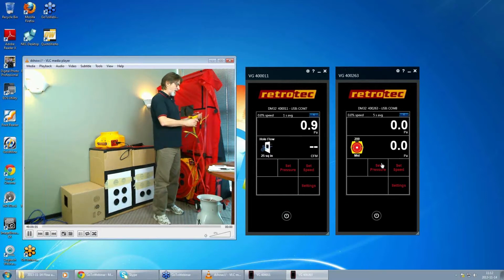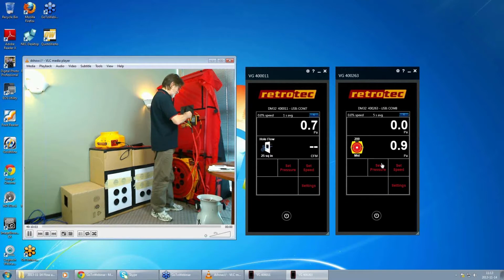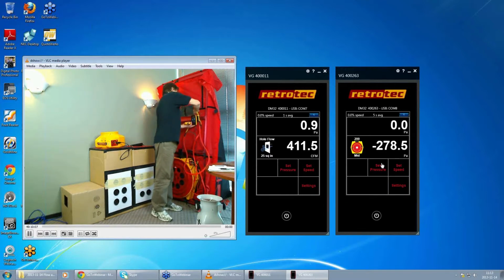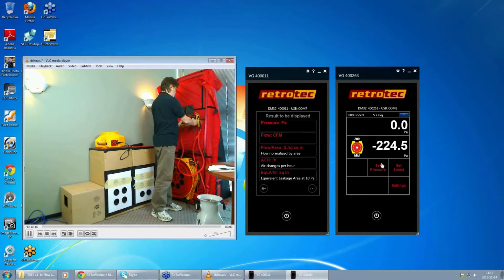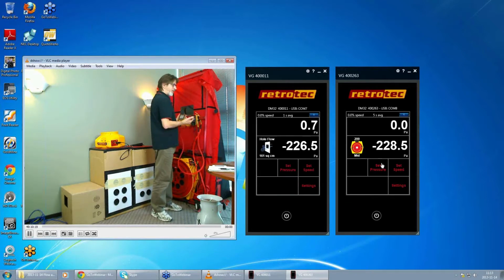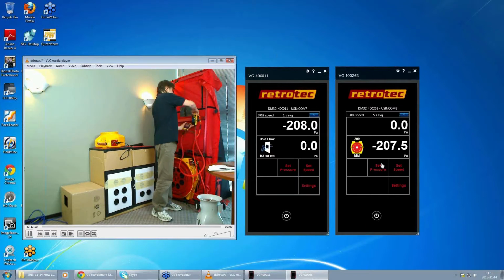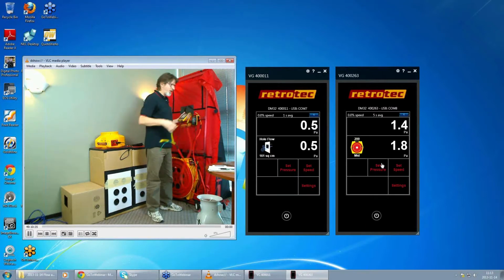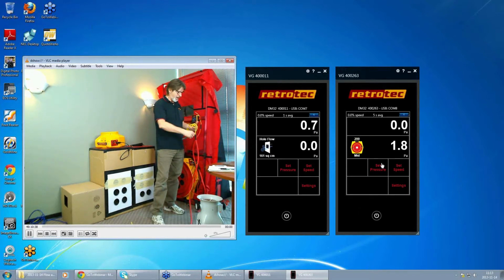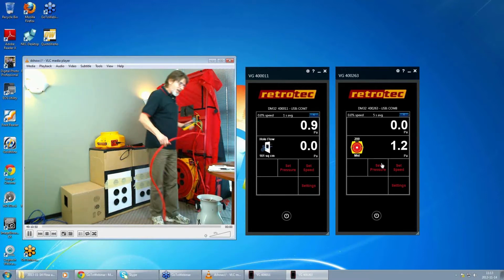You can also check this gauge between this gauge and another gauge to make sure that, in fact, we can do that right now. We can check this gauge here against this gauge over here. And we have to change this to pascals, of course. So 224, 225, it means this gauge is the same as that gauge. We can check the other channel in the same way. So we've got 208, 207. So this is meaning that both of these gauges are in good shape. I know there's a lot of talk about getting gauges calibrated on a regular basis. I think that's a lot of wasted time and money. And a gauge check should be something that gets performed on a regular basis. So that takes care of the gauge check part.